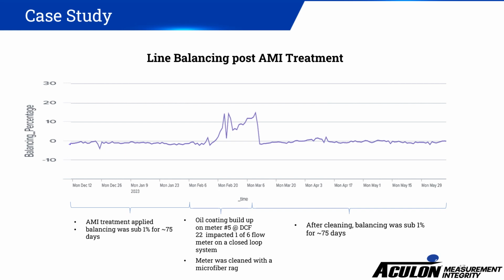We then again saw, after 7 to 9 days, our balancing started to drift to 10+%. We then rolled out and cleaned our control group meters, placed them back into service, and again within 9 days they were creeping out of balance. We then placed the treated meters back into service and have continued to see good performance over the last few months.